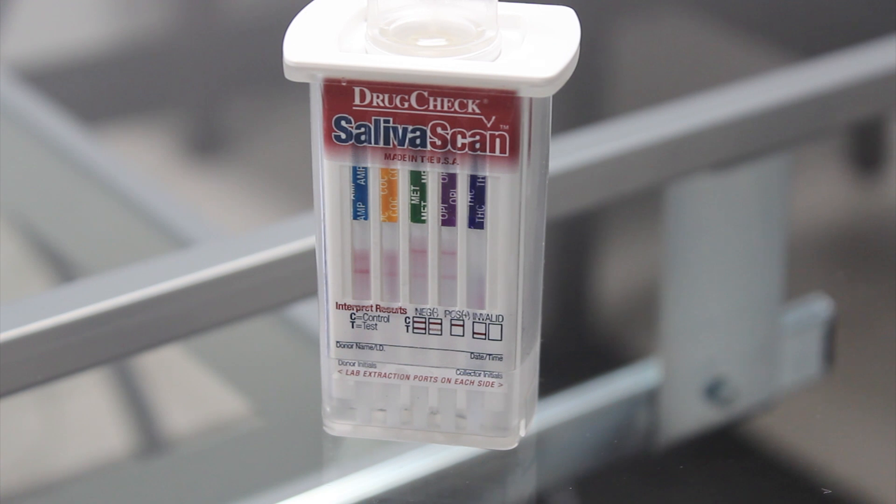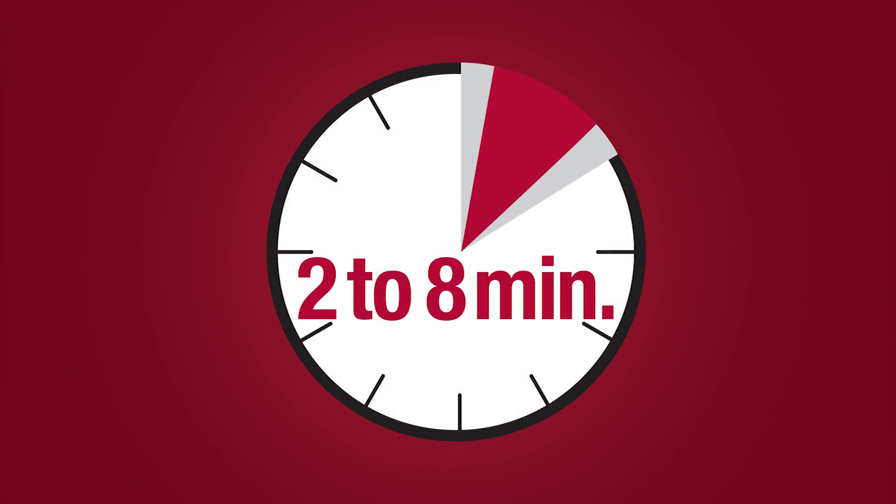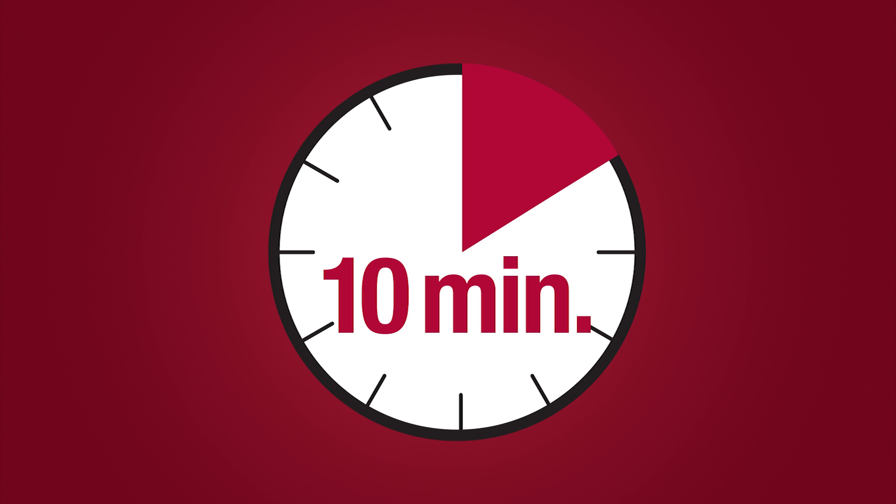Interpreting results. Once the CTRL line is visible, the test is ready to be interpreted. Typically, this occurs in 2 to 8 minutes. Read presumptive positive results at 10 minutes. Do not interpret results after 20 minutes.